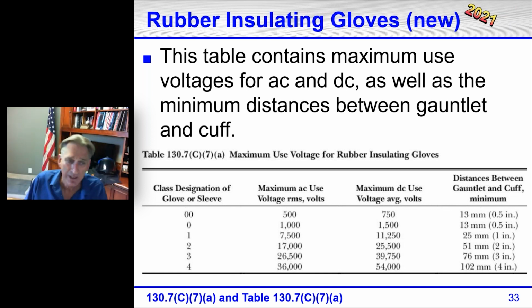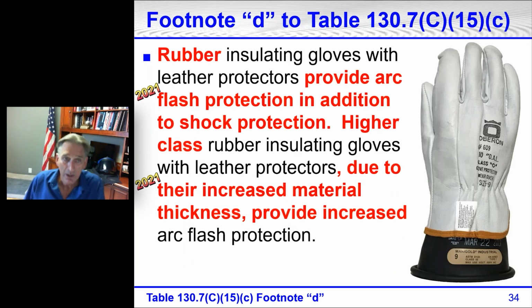So this is a new table. It could be found before, but now it's in 70E, which makes it nice and easy to find. There's a footnote with a little wording change. Rubber insulating gloves with leather protectors provide arc flash protection in addition to shock protection. Higher class rubber insulating gloves with leather protectors, because of the increased material thickness, provide increased arc flash protection.